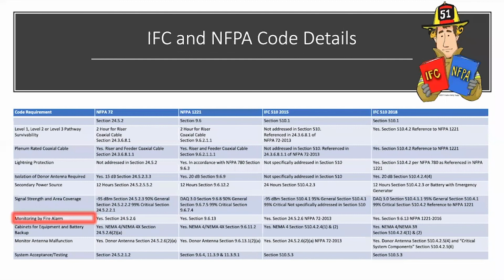Systems must provide alarm outputs for specific conditions or failures affecting their performance. These are tied into the building's fire alarm system for monitoring. There may also be a separate alarm annunciator adjacent to the main fire alarm panel. Equipment and batteries must be housed in cabinets which are NEMA 4 rated. This ensures integrity against water intrusion while firefighting is underway. NFPA has always required monitoring for malfunction of the donor antenna, as this is the operating link for an in-building system. The latest IFC code also requires monitoring of additional critical system components.